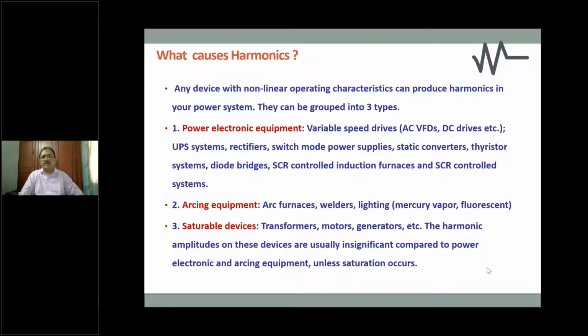Nowadays you will find the growth of variable speed drives is also as big as the growth of motors, plain motors itself. That goes on to prove that not only for new motors, also for existing motors, VFDs are chosen for energy saving. So as an energy saving opportunity available either by a mechanical engineer in terms of fans, pumps and compressors, or in terms of the process engineers whose process requirement can be optimized by varying the speeds and optimally reducing the speeds, the energy saving is a resultant benefit apart from meeting the requirement of the process. Therefore, variable speed drives are very common.